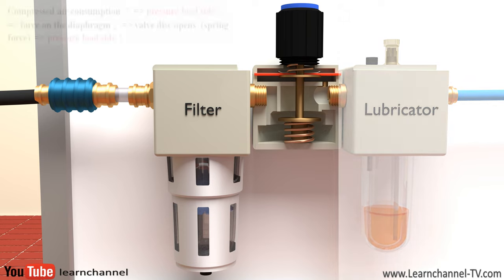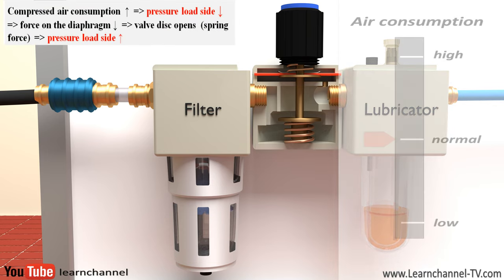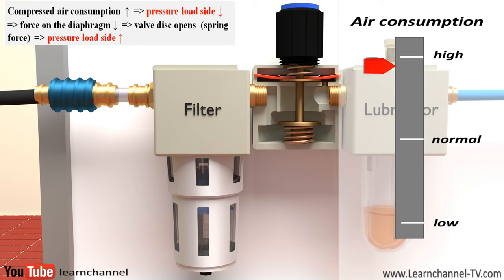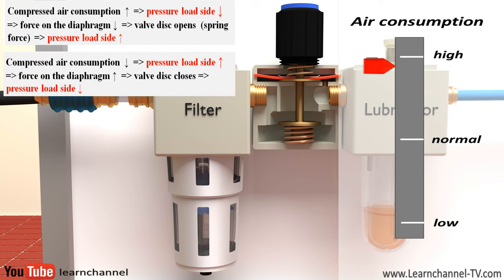Whenever more compressed air is consumed, then the pressure might drop on the load side. Therefore, the force acting on the diaphragm decreases. Due to the spring force, the diaphragm is pushed together with the valve disc in such a way, permitting more airflow to the secondary side and increasing the pressure again. If the outlet pressure is too high due to less consumption, then the load pressure increases. Therefore, the force acting on the diaphragm increases, the valve disc closes, less air flows, and the output pressure must decrease.